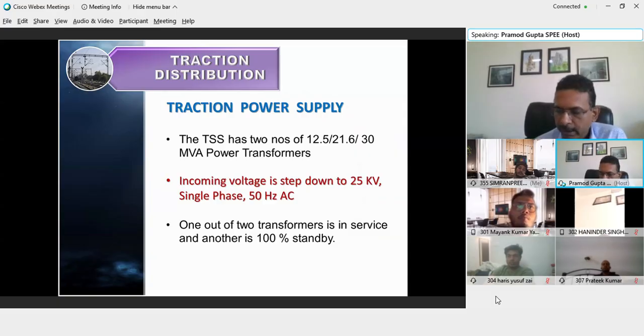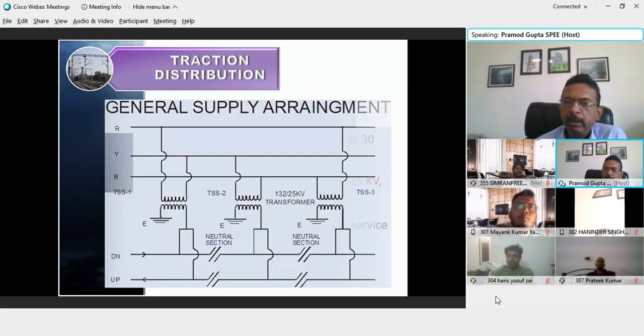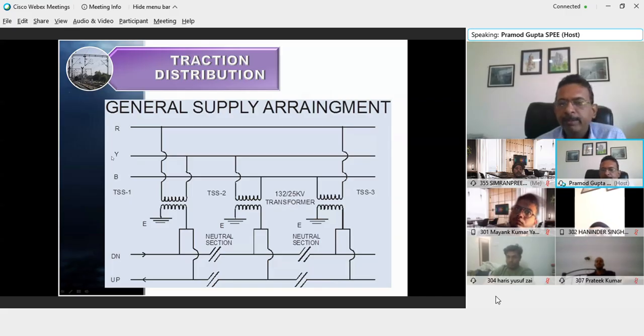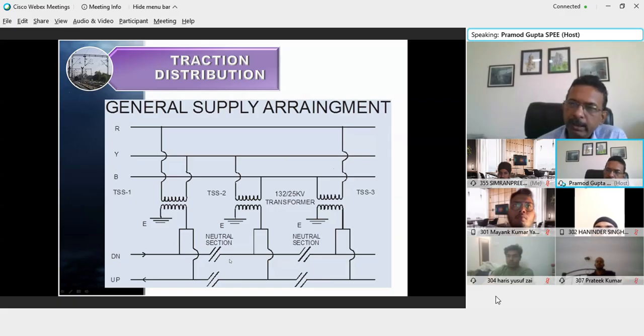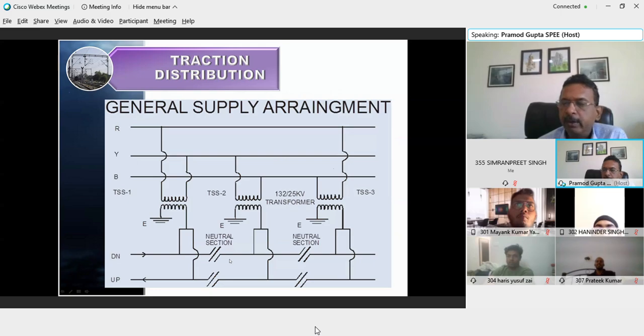So we have two independent incoming power supplies, and we also have two independent transformers to take care of the load. This is how the general power supply arrangement looks in the TRD system. On this screen, I have shown three TSSs: TSS1, TSS2, and TSS3. The transformer I mentioned is a 132 by 25 kV transformer, and the incoming power supply is connected to three different phases before extending the power supply to Indian Railway. The power supply from one TSS cannot go endlessly to the other side of the country. It has a limit beyond which we cannot extend the power supply.